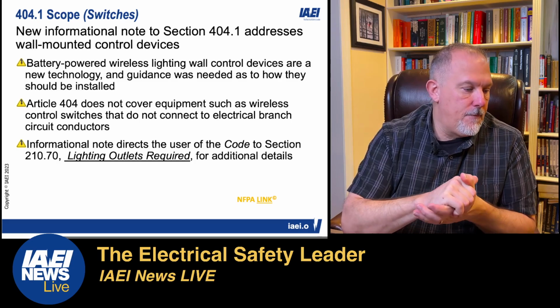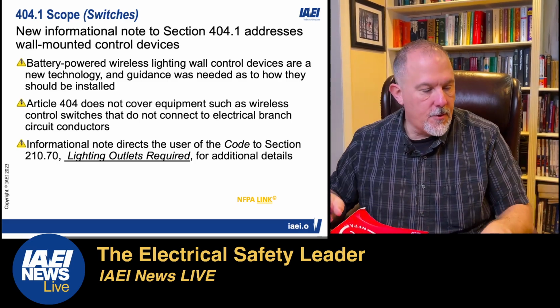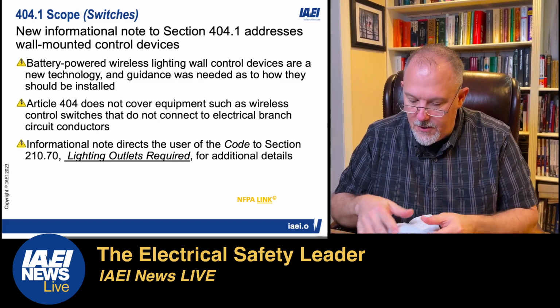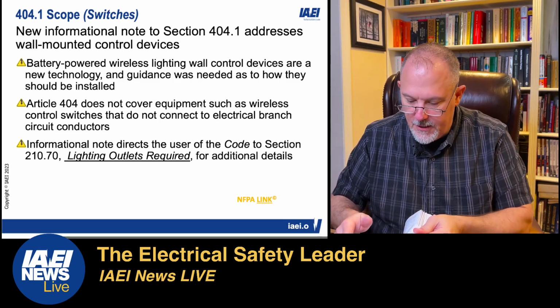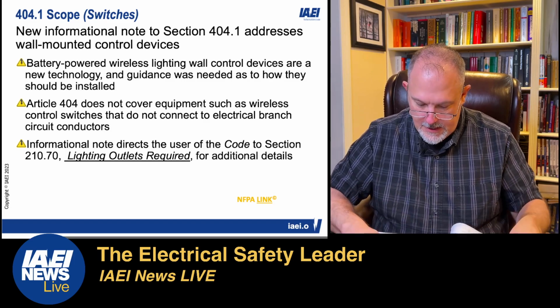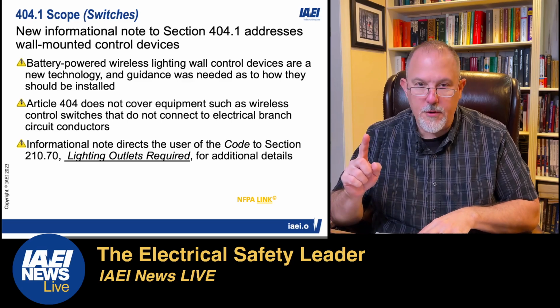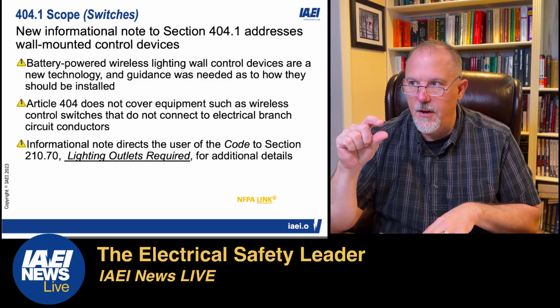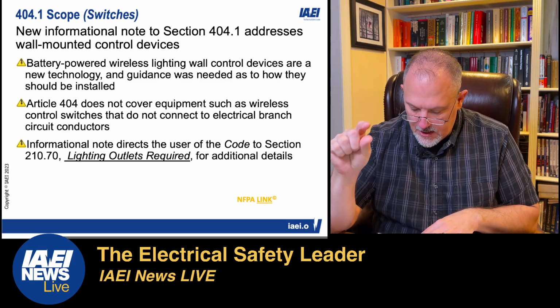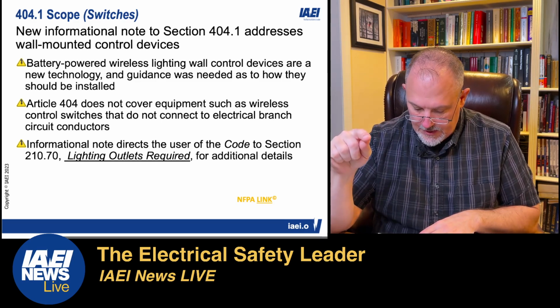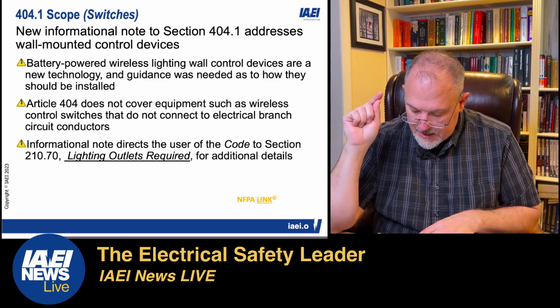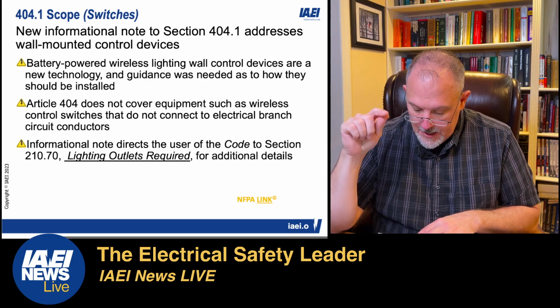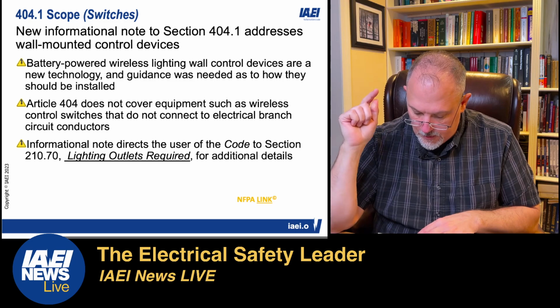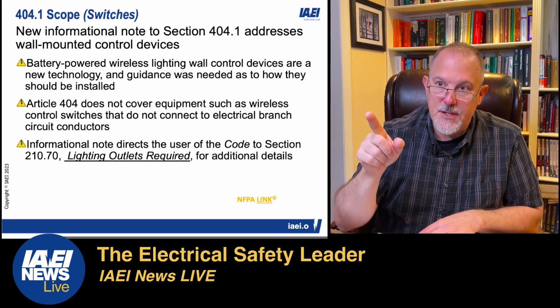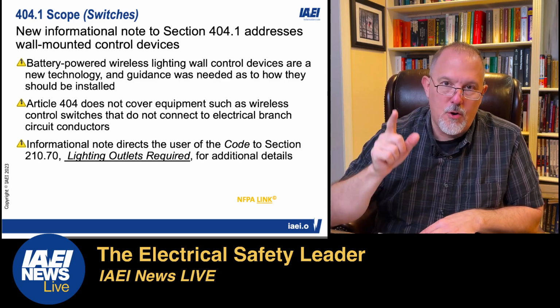So I'm going to grab the 2023 book because I want to read to you the scope. Oh yea, though I read from the book of the NEC. All right, that's 402. 404 switches. This is the first portion of the text. It says, this article covers all switches, switching devices, and circuit breakers used as switches operating at 1,000 volts and below, unless specifically referenced elsewhere in this code for higher voltages. This article does not cover wireless control equipment to which circuit conductors are not connected, and that is the battery-powered wireless lighting wall control devices.